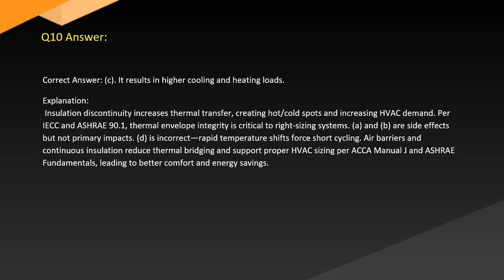Answer. Correct answer: C. It results in higher cooling and heating loads. Explanation. Insulation discontinuity increases thermal transfer, creating hot-cold spots and increasing HVAC demand. Per ASHRAE 90.1, thermal envelope integrity is critical to right-sizing systems. A and B are side effects but not primary impacts. D is incorrect. Rapid temperature shifts force short cycling. Air barriers and continuous insulation reduce thermal bridging and support proper HVAC sizing per ACCA Manual J and ASHRAE Fundamentals, leading to better comfort and energy savings.